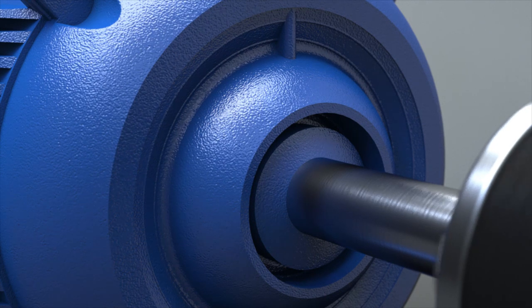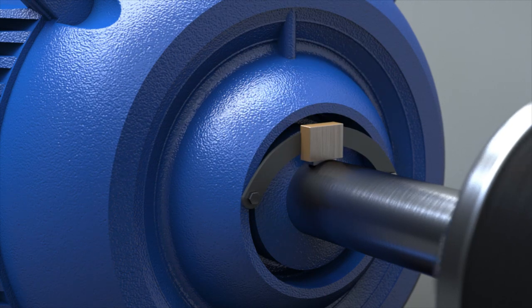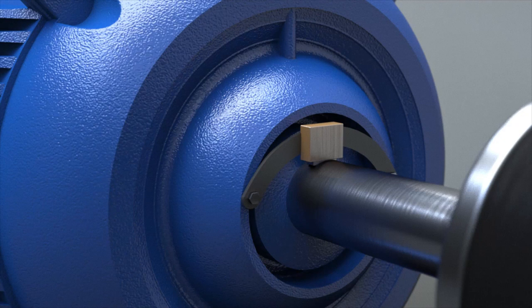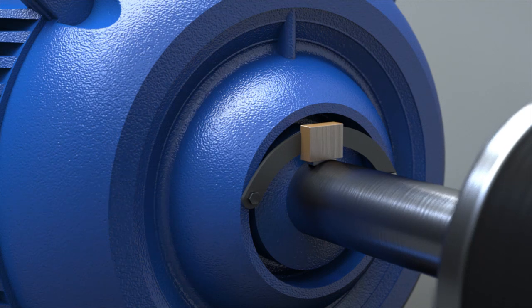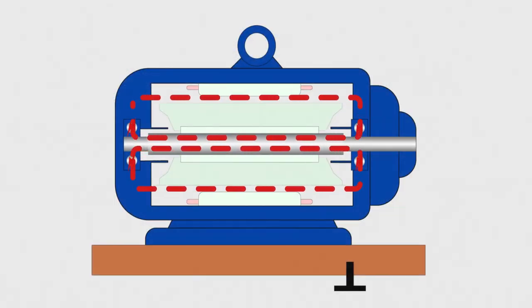If a machine is rated at less than 100 horsepower, a carbon fiber brush may be attached to a shaft grounding ring, also called a split ring, solid ring, or a press fit, and installed on the drive side of the shaft. This will effectively redirect the current to ground and will avoid arcing between the bearing components which could result in bearing failure.